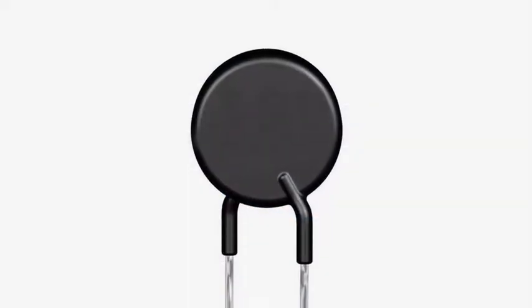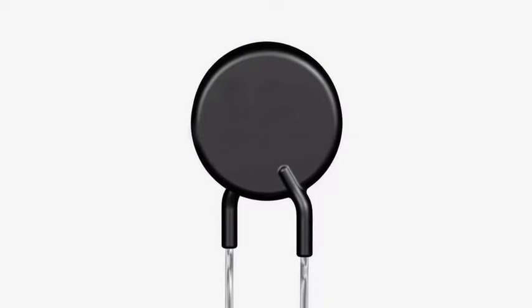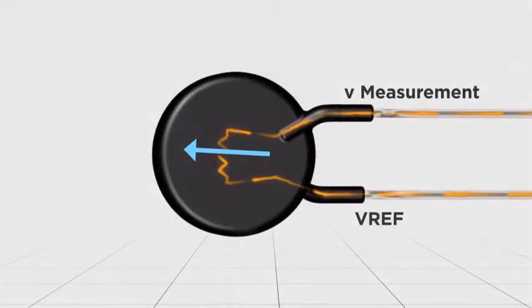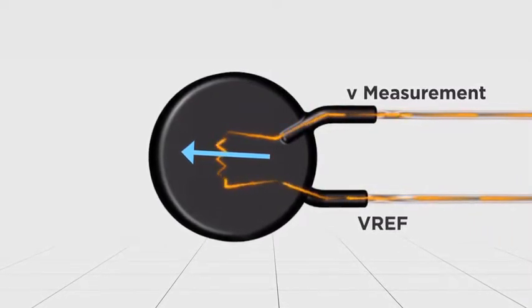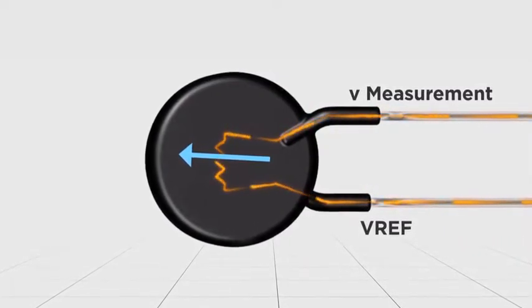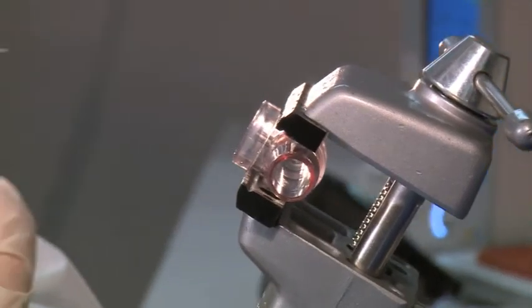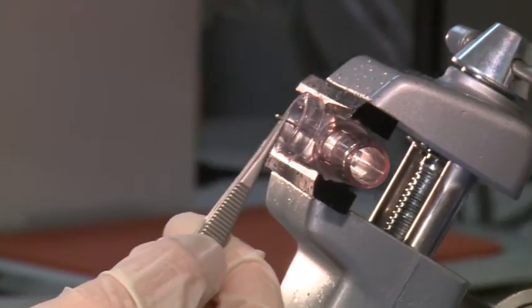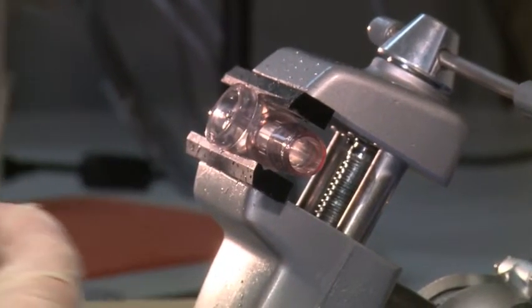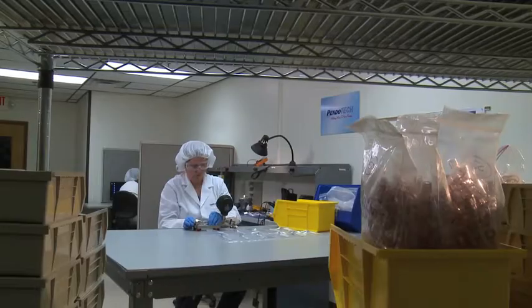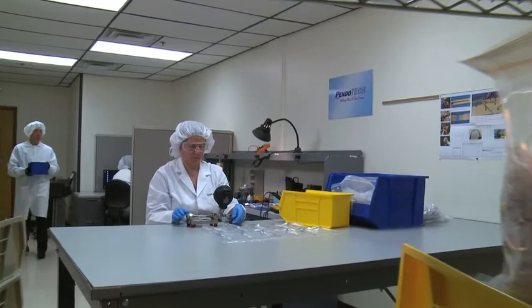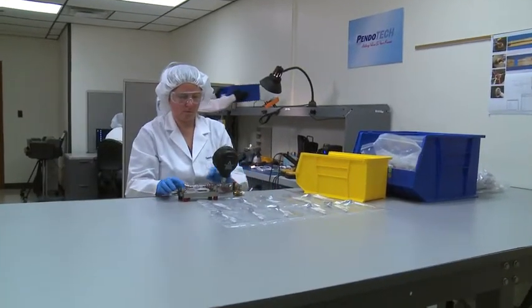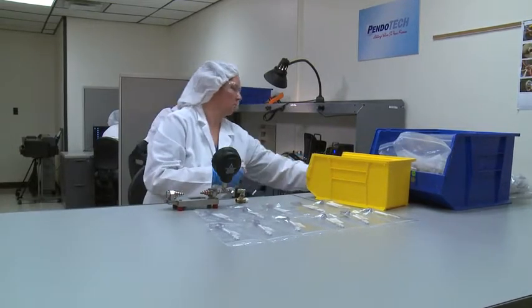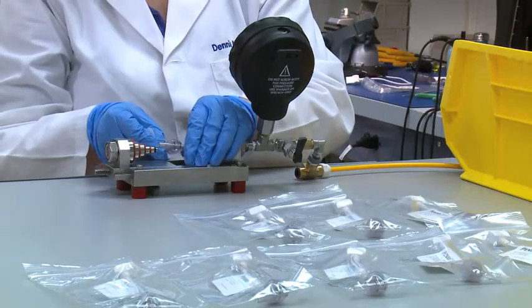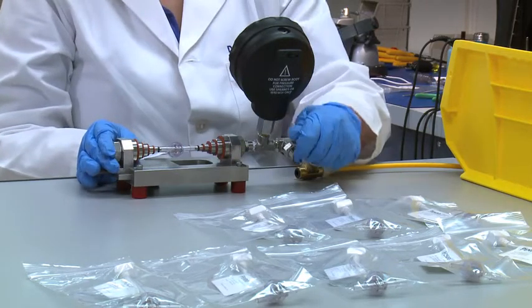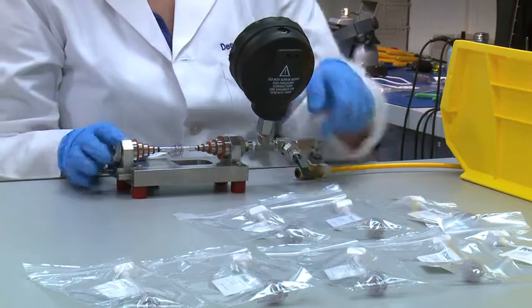No calibration is required on the thermistor because the output signal from each thermistor is manufactured to tight tolerances. It is then tested to be within its defined accuracy specification before being made into a sensor. The assembly process involves installing the thermistor into one of the conductivity electrode tips, then securing the electrodes into the molded product body. Assembly and final testing is done in a clean and controlled environment, rated ISO Class 7 in an ISO 13485 facility. Completed sensors then undergo a number of tests in manufacturing, and each sensor comes with a certificate of quality to back up the 100% testing.